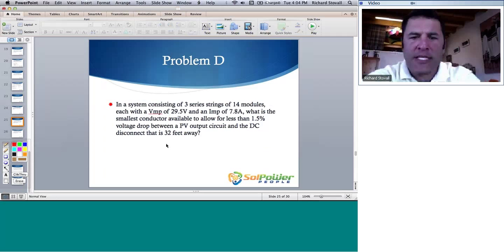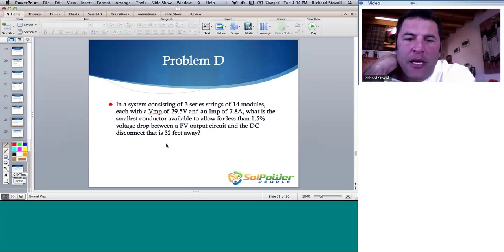That was problem C. All right, so now we're on problem D. The system consisting of three series strings of 14 modules, each with a VMP of 29.5 and IMP of 7.8, what is the smallest conductor available to allow for less than 1.5% voltage drop between the PV output circuit and the DC disconnect that is 32 feet away?